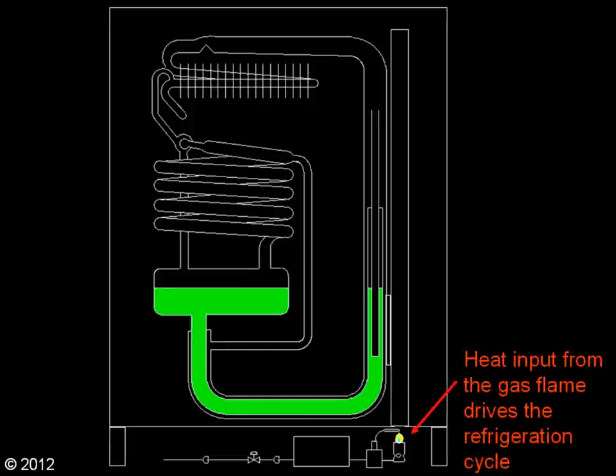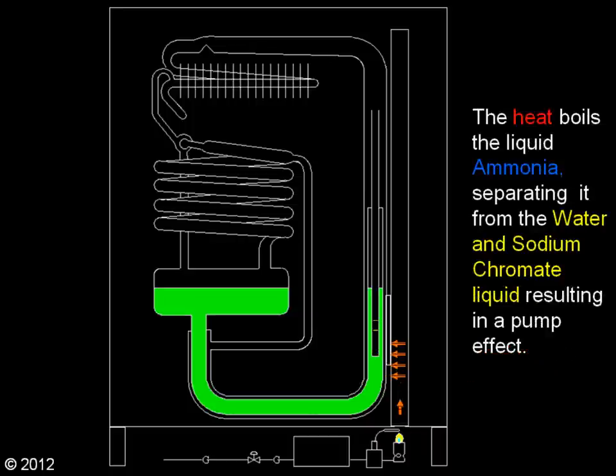Heat input from the gas flame drives the refrigeration cycle. Heat enters the boiler. The heat boils the liquid ammonia, separating it from the water and sodium chromate liquid, resulting in a pump effect.